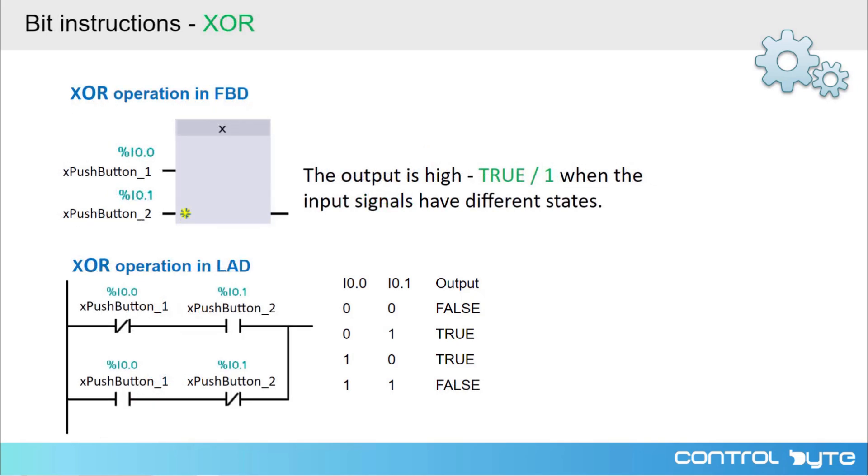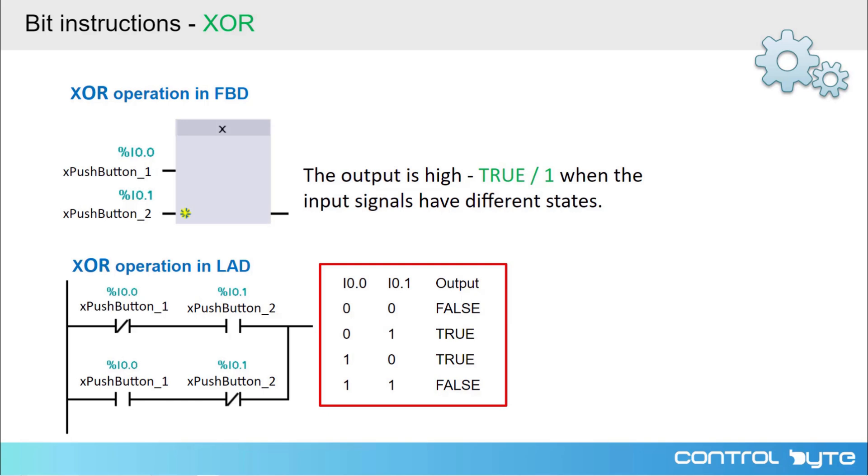The next bit logic operation is the XOR instruction. This is an instruction that in LAD language has the following form. Here we use both NO and NC contacts to generate the desired result. What does this instruction look like in FBD? It is a block with an X mark. Let's look for the logic of this instruction. The instruction returns a logical zero if the input has two logical zeros or two logical ones.